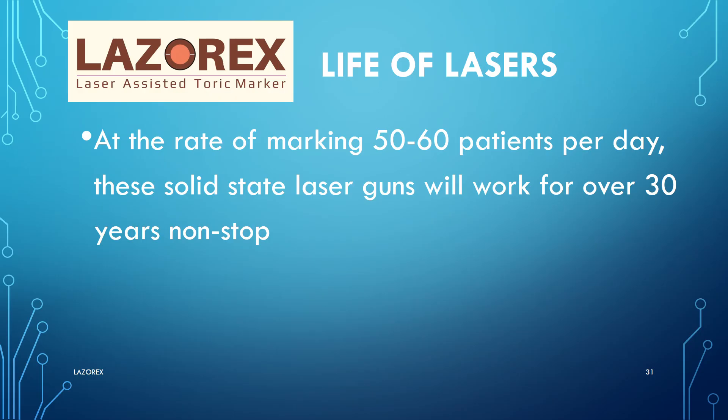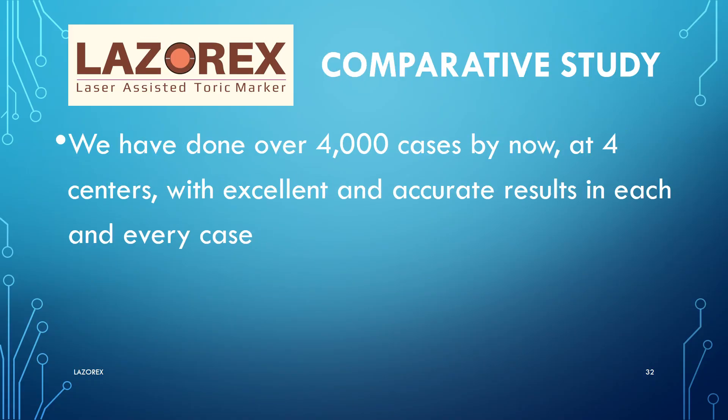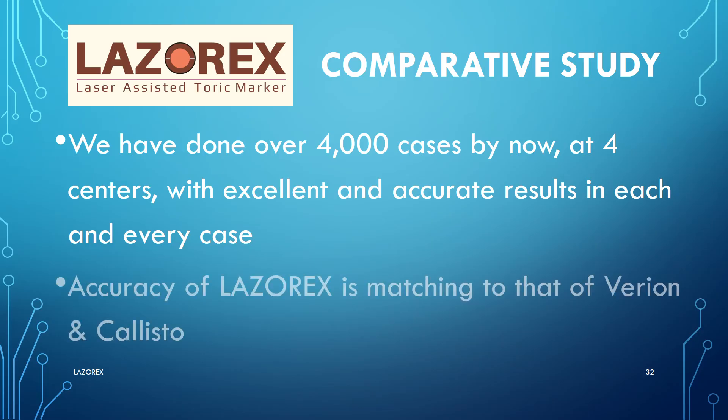At the rate of marking 50 to 60 patients per day, these solid state laser guns will work for over 30 years non-stop without any periodic maintenance, AMC, or CMC. We have done over 4,000 cases with LAZOREX at four centers with excellent and accurate results in each and every case. The accuracy of LAZOREX is matching that of Verion and Callisto.